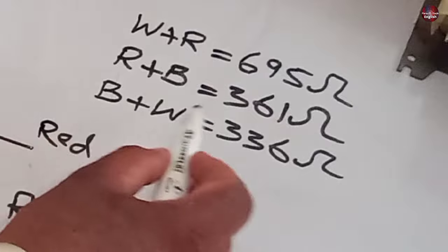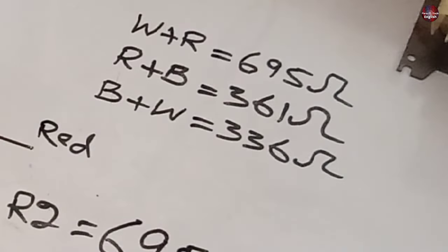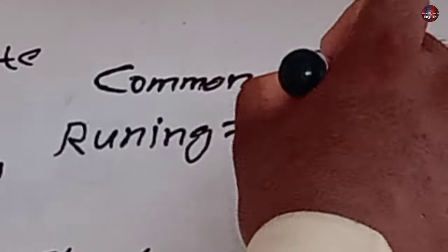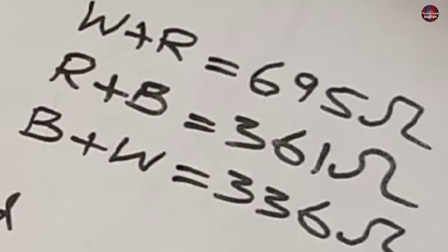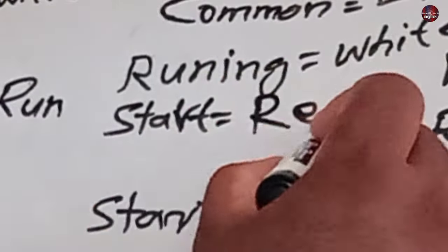It means the value of the wire with the lowest resistance will be the run winding. Running winding is the white wire. The starting always has a medium value. This means the start is the red wire.